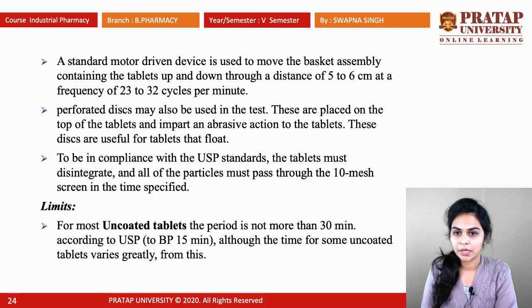To be in compliance with the USP standard, the tablet must disintegrate and all of the particles must pass through the 10 mesh screen in the time specified. There are limits for different categories of tablets. First is the uncoated tablet. For uncoated tablets, the disintegration time is not more than 30 minutes according to USP. According to British Pharmacopoeia it is 15 minutes, and according to United States Pharmacopoeia it is 30 minutes.